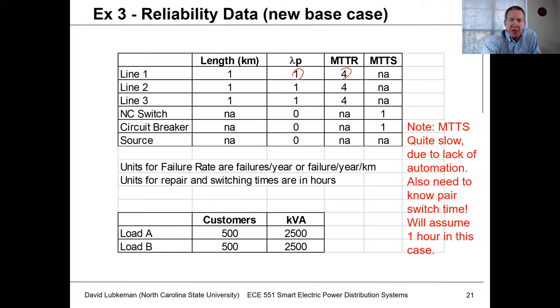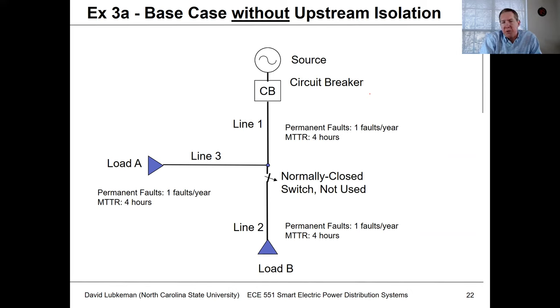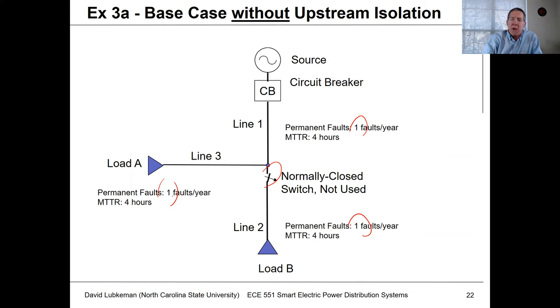The switching time of one hour is a large number, and to get it down we'd need automated switching, which we'll get to toward the end of this example. For the base case, we assume that even though the switch is there, it's not used. Based on the failure rate, we have one fault event per line section per year.